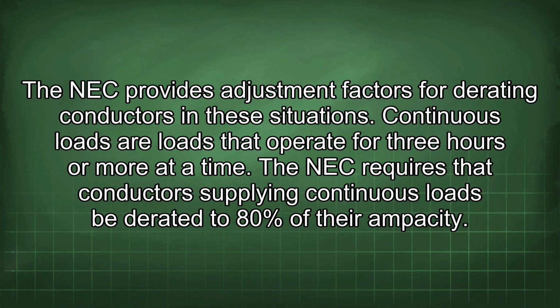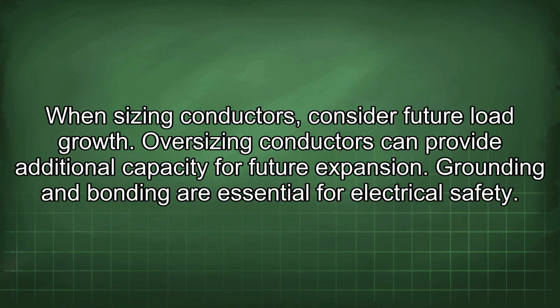Continuous loads are loads that operate for 3 hours or more at a time. The NEC requires that conductors supplying continuous loads be derated to 80% of their ampacity. When sizing conductors, consider future load growth. Oversizing conductors can provide additional capacity for future expansion.